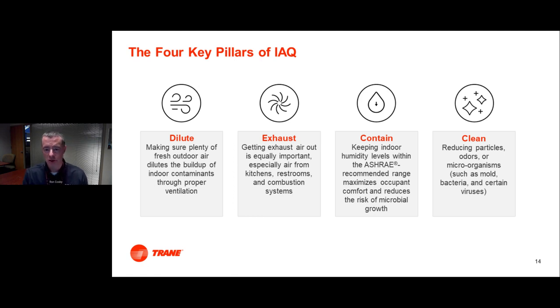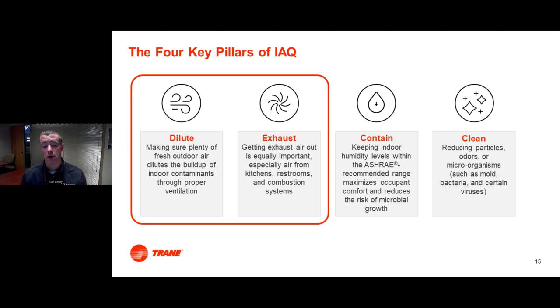Now, each of these pillars can be used to mitigate risk within a building. And Jeff talked about how each building is going to be different, so you may have different mitigation strategies based upon the type of building and what may already exist for that building in place, and depending on what type of contaminant you may want to go after. We're going to talk a little more on dilution on the next slide. But just to start, dilution is effectively just bringing in outside air to reduce the overall concentration of whatever contaminant you're trying to remove. Going hand in hand with dilution is exhaust. It's conservation of mass. You bring something in, something's got to go out.